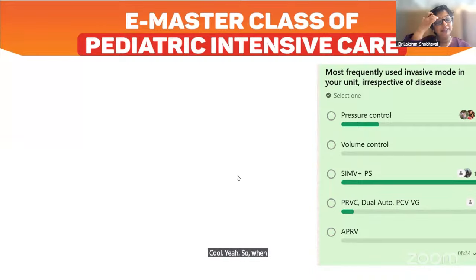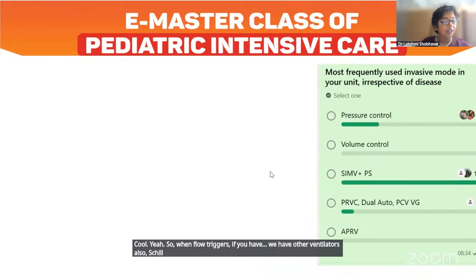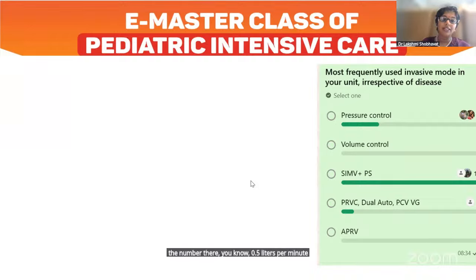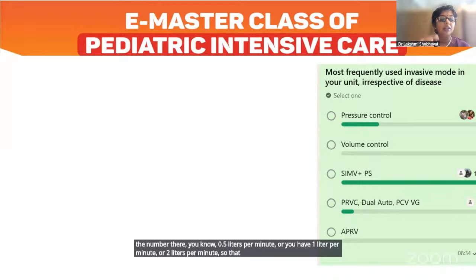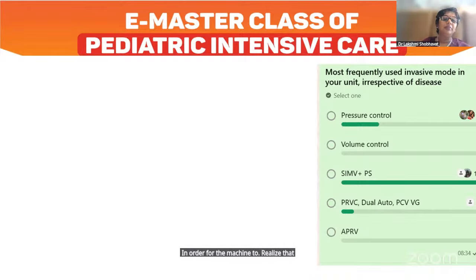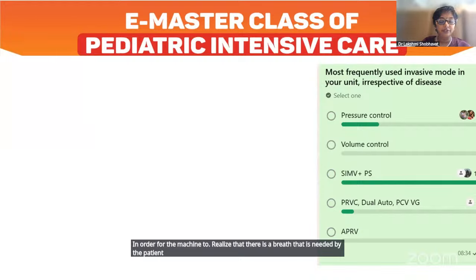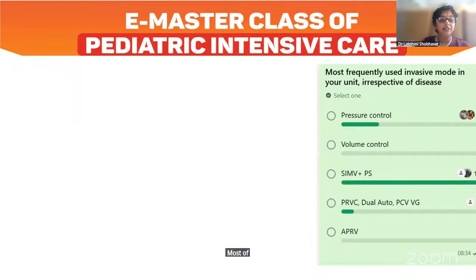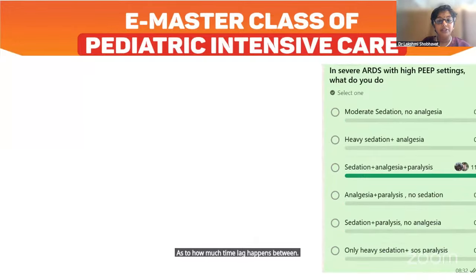We have other ventilators also, Schiller and Bella Vista. In those, if you have to set a flow trigger, you have a number there: 0.5 liters per minute, or 1 liter per minute, or 2 liters per minute. That is the negative flow the patient has to generate for the machine to realize that the patient needs a breath. You also have to see where the flow sensor is. Most of these machines have flow sensors right at the machine end and not at the patient end, so that makes a difference to the time lag between when the patient needs the breath and when the machine gives it. There are some millisecond differences.